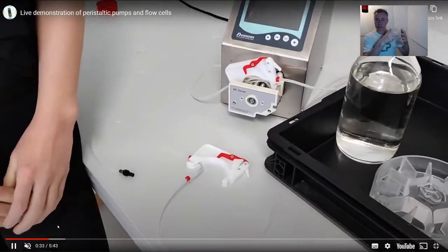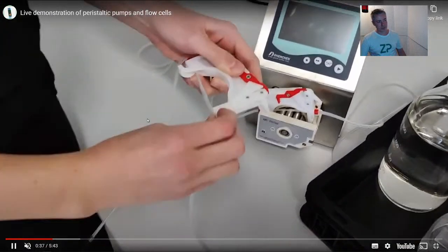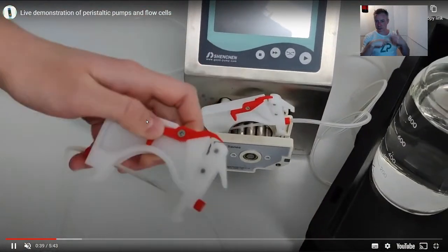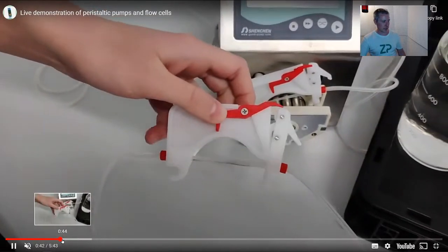In this video, we describe a pump and we describe a flow cell. It's a peristaltic pump, so it has tubing. The tubing gets squashed and it pumps solution. And I think this talks a little bit about Zimmer Peacock, because the group that Saran is in, who's online tonight, also does a lot of mechanical work as well. One of the things they've done is manufacture a flow cell, so that we have the pump and we flow through a flow cell, and it allows us to put sensors into the flow stream so that we can essentially change the solution or bring sample to the sensor.